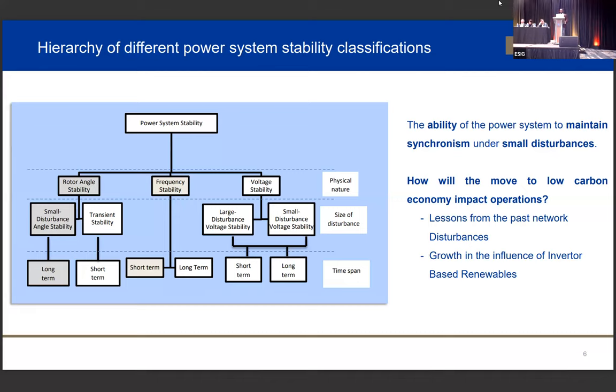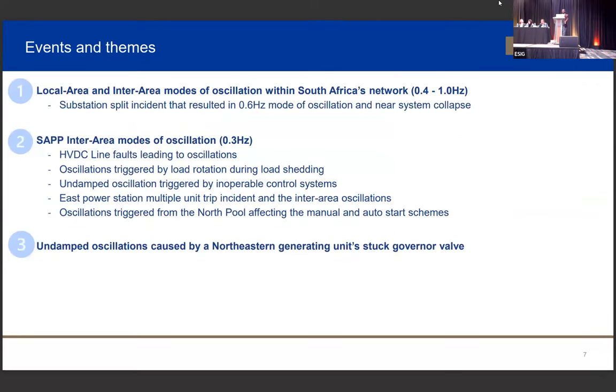So if we ask ourselves, how will the move to a low carbon economy impact operations? Like we showed, the dominant type of power station is in the Northeast, and renewables are in the coastal areas. So how will the growth in the influence of inverter-based renewables play out? I'm going to give you examples of the incidents that we have recorded. The first one is a local and inter-area mode of oscillation within South Africa. The oscillation there is 0.4 to 1 hertz. Then in group two, we grouped by groups, it's a SAPP inter-area mode of oscillation, normally 0.3 hertz. There are about 5 different examples of how the mode was excited.